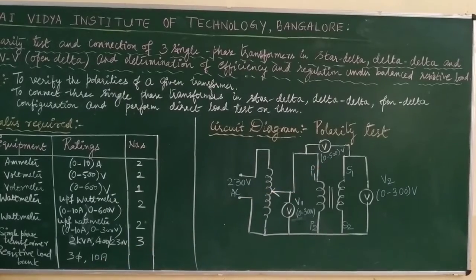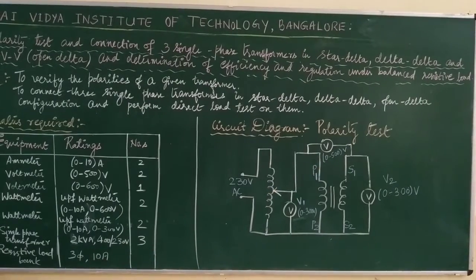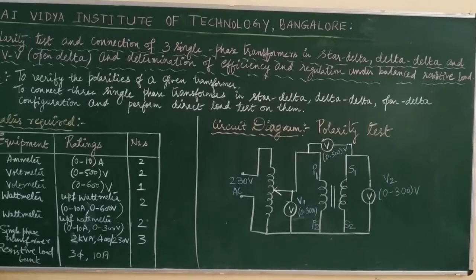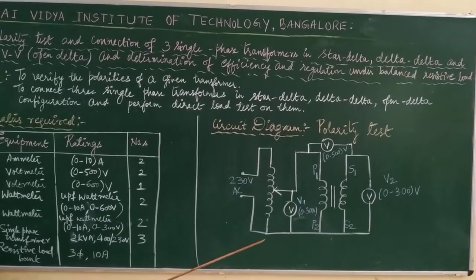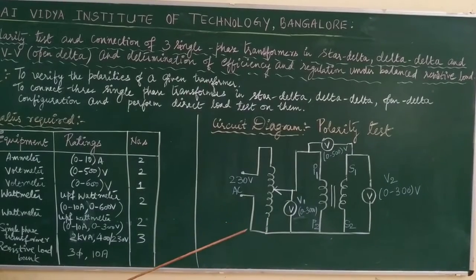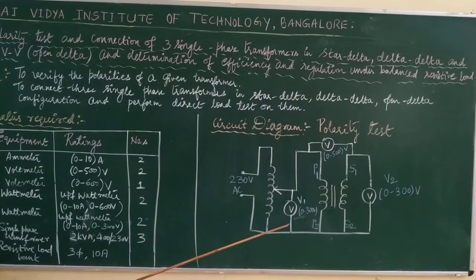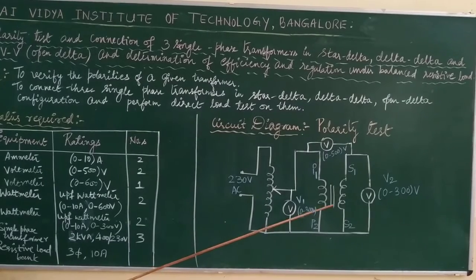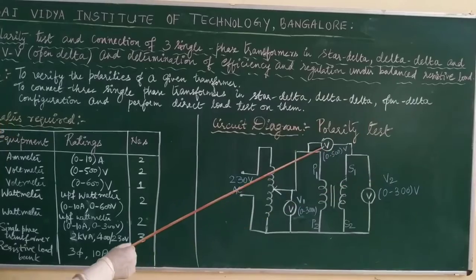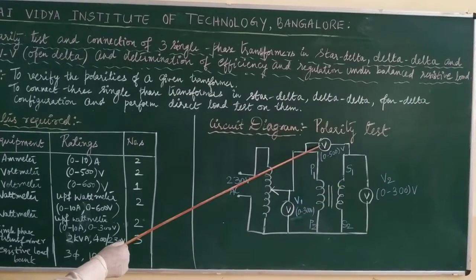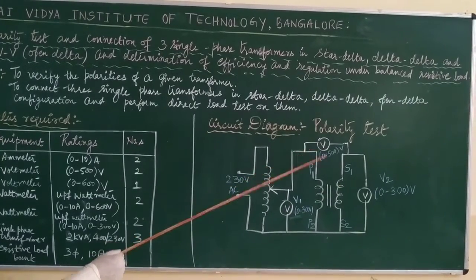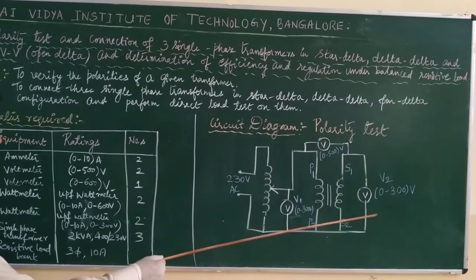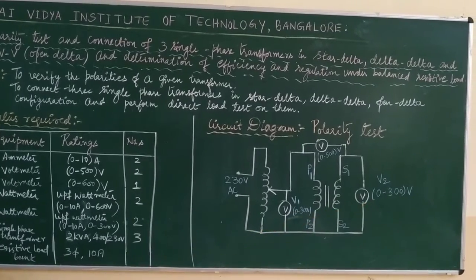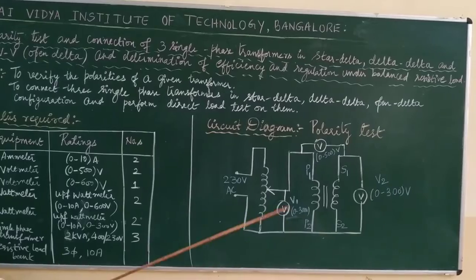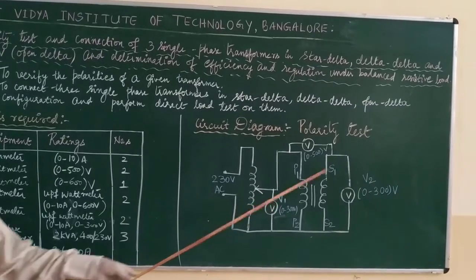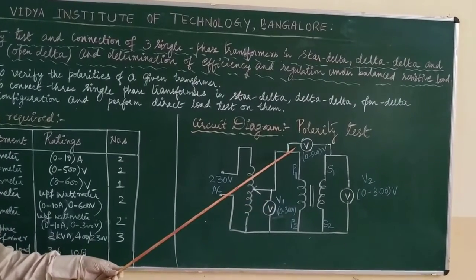Whenever we come to polarity test, we have additive polarity and subtractive polarity. Once the circuit is connected, we check the reading V1, we check V2, and then we check the third voltmeter, which we can call V3. If V3 reads the sum of the readings of V1 and V2, then it is said to be additive polarity. And in case it reads V1 minus V2, it is said to be subtractive polarity.